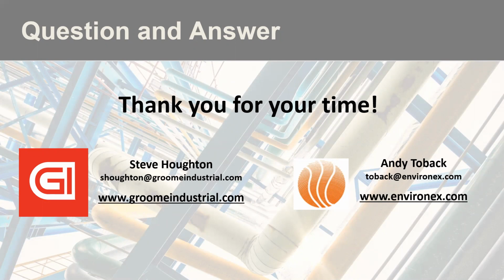I think that this one is very direct and important. It's right, great aftermarket question. Whether you're changing any major variable from your lances to your catalyst to turbine upgrades themselves, every factor changes there, and you certainly want to retune. Your gas path might change. Your pressure is going to change. There's a million different things to consider, and you definitely want to retune.